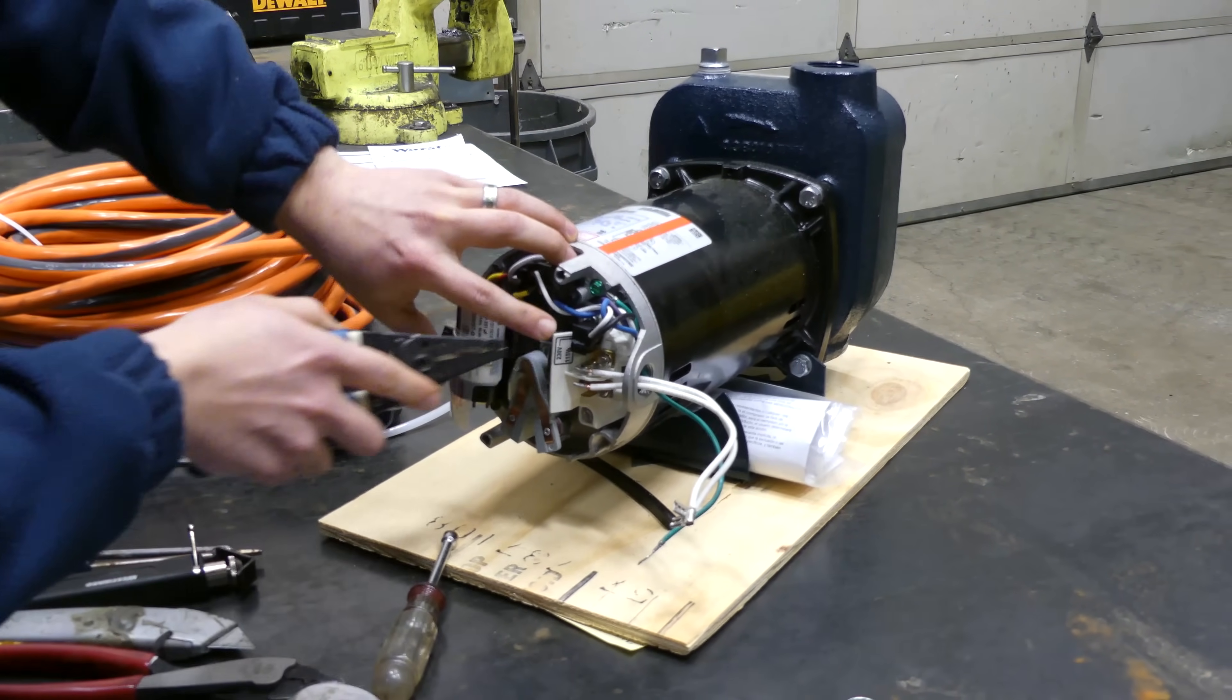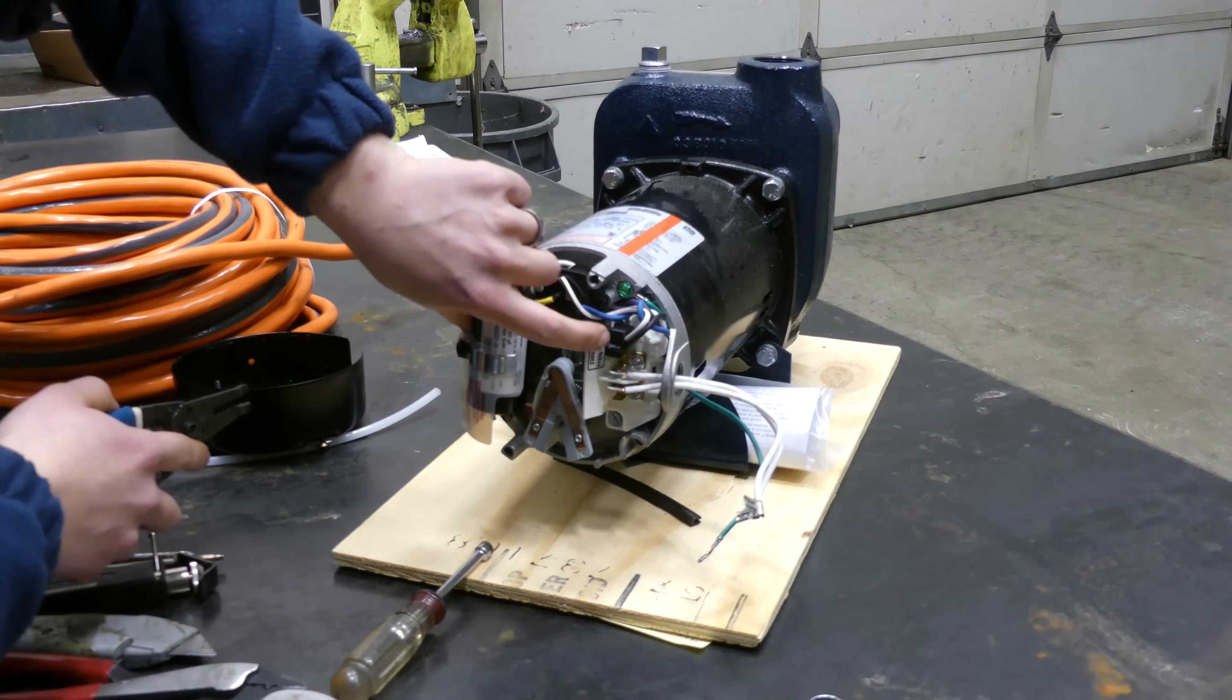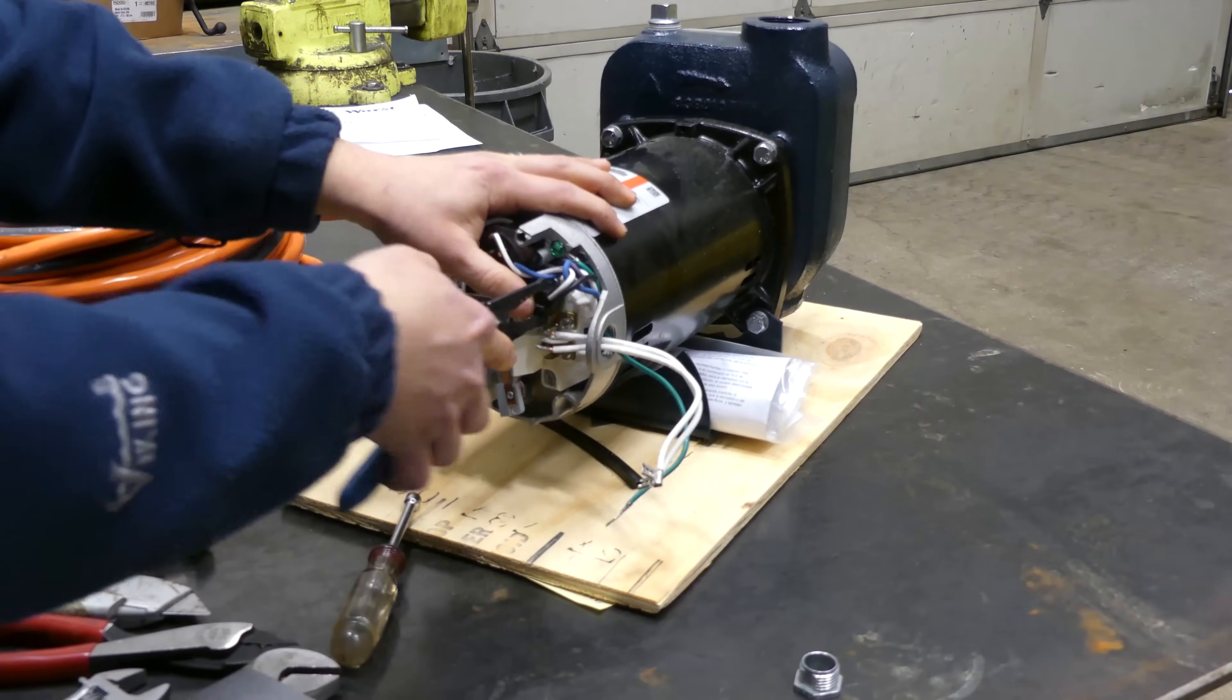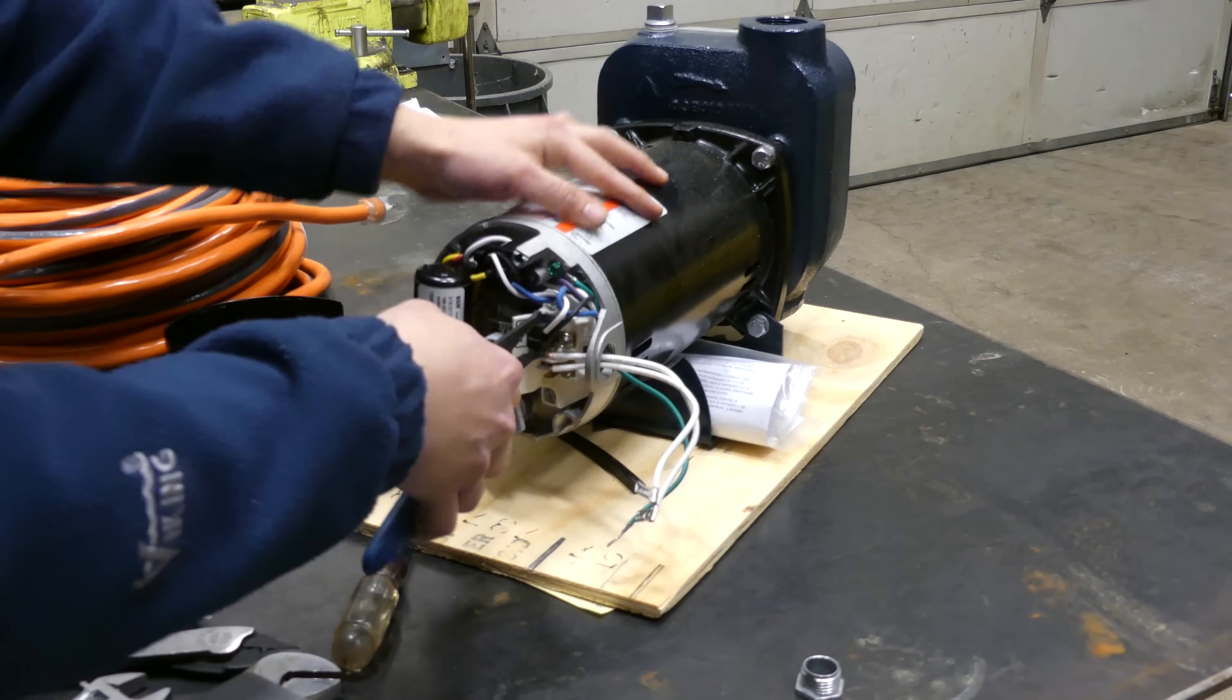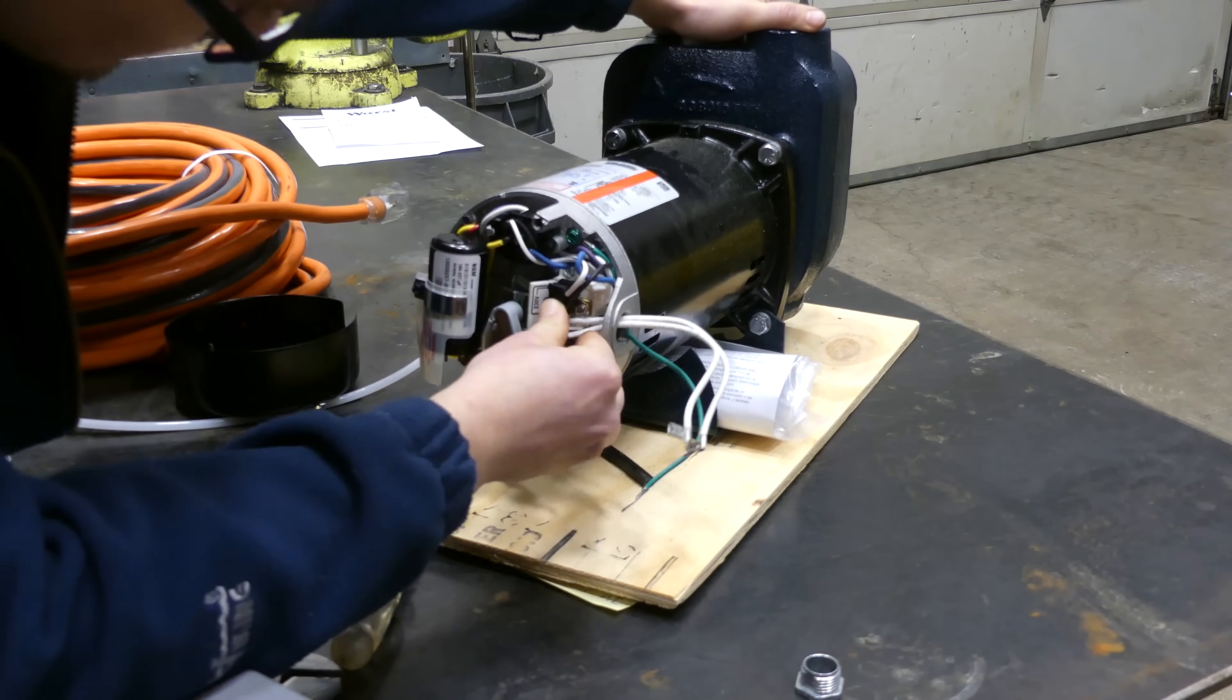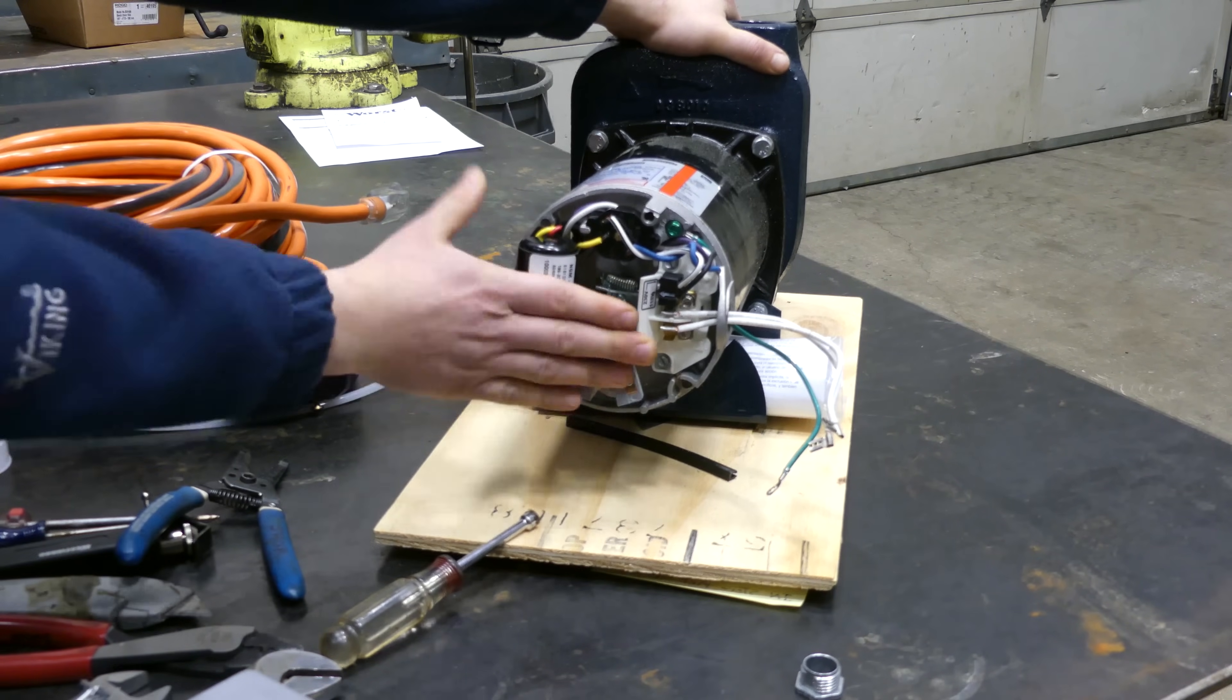Right now, you can tell there's a little white arrow that's pointing to the 230 volt here. So we need to move this to where the white arrow is pointing to 120 volt. So I'm just going to grab a hold of it here, tug it off, move it down, make sure we're lined up. It looks good. Push it all the way down. And that looks great. So now we know we're switched over to 120 volts.